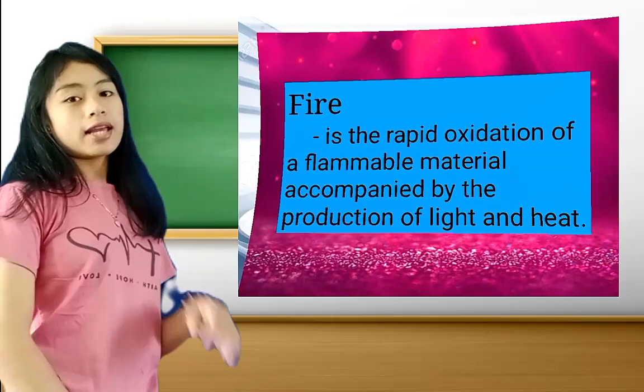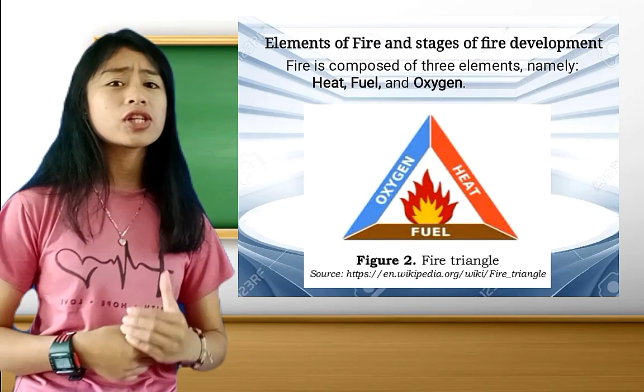Let us move on to the elements of fire and stages of fire development. Fire is composed of three elements, namely heat, fuel, and oxygen. These three elements form the fire triangle, as seen in figure 2. A fire starts when the fuel is heated from an external source and reaches its ignition temperature, and then oxygen reacts with the fuel to sustain the fire. Once a fire has started, it will continue to burn until an element of the fire triangle is removed.